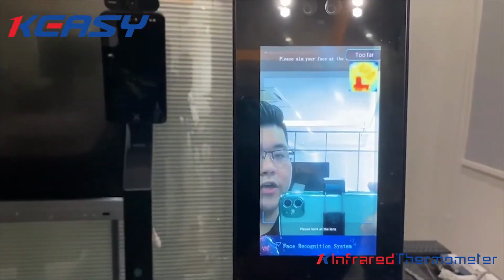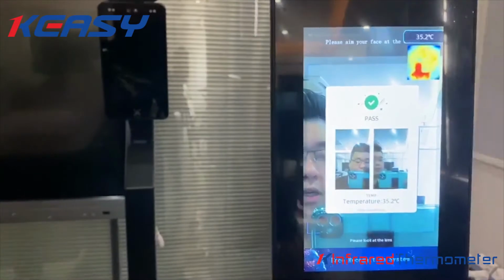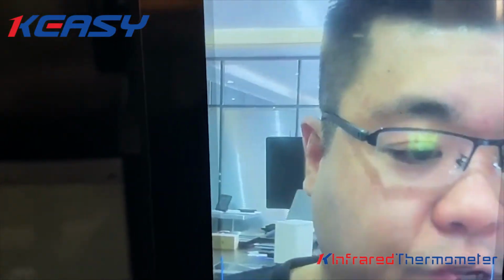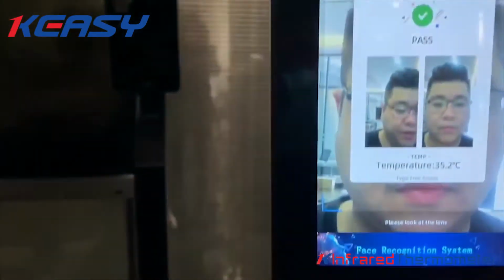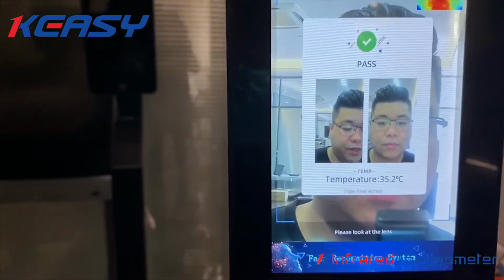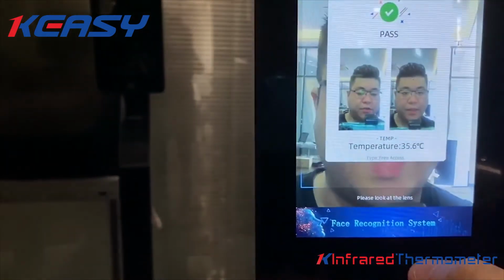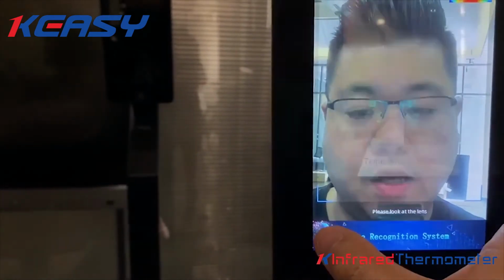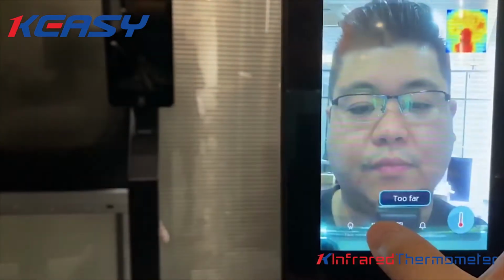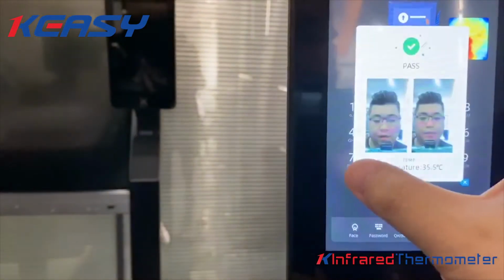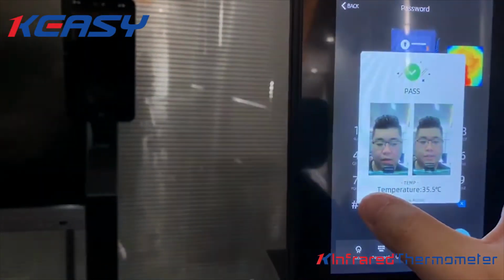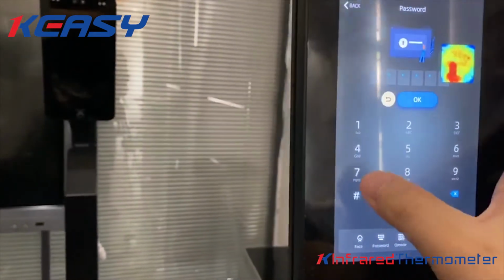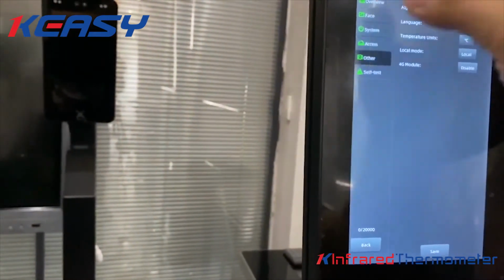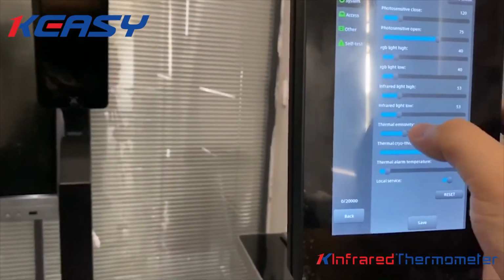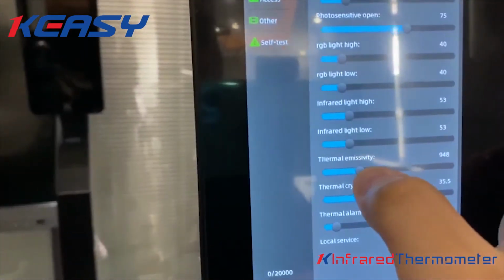Okay, after we change the value of the temperature emissivity, now we'll test the temperature again. And here it shows my temperature is 35.2. So it means the value already got higher, but it is not accurate. So we need to adjust one more time until the temperature is similar to the thermometer. Okay, we need to set the value lower.